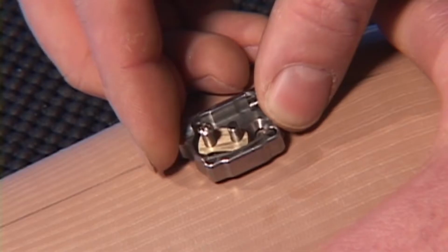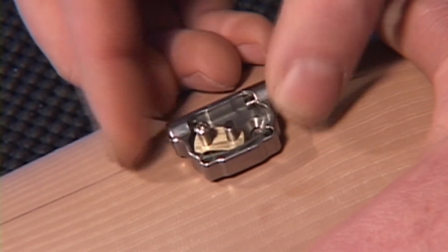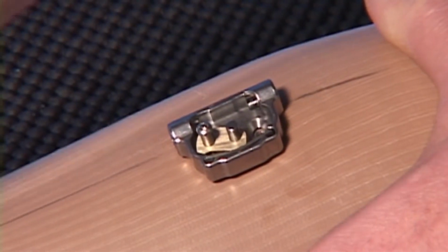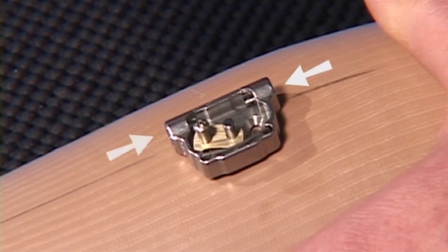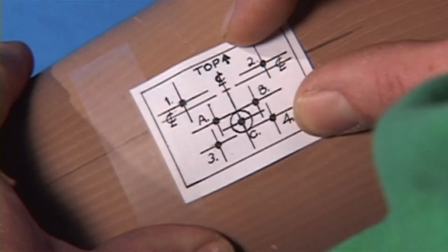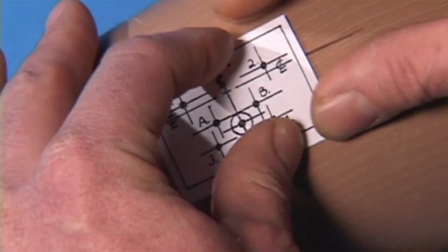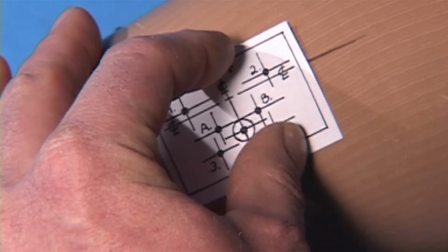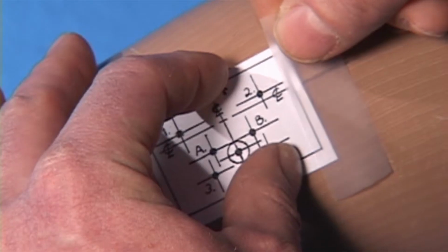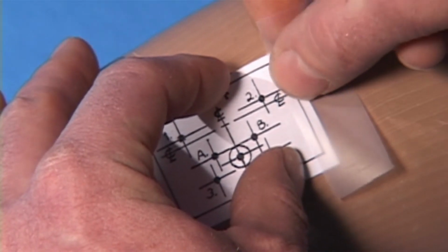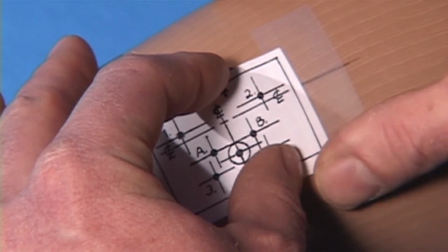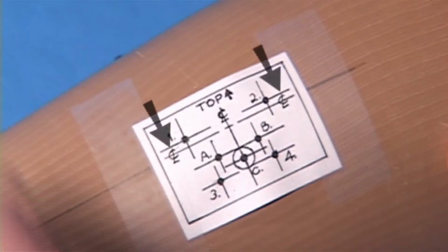Position the stainless structural base over the center line at the optimal location and mark its position. The cable inlet and outlet holes in the structural base should align with the center line, with the bulk of the base being lateral or below the center line. Attach the template to the prosthesis at the location marked for the structural base using a spray mount type adhesive or clear tape. Make sure to align the center line of the template with the marked center line on the prosthesis.